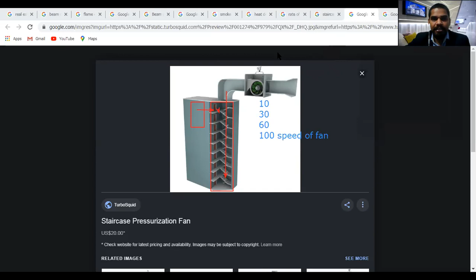For example, if only three floors are affected, it will run the fan at 10% speed. If 30% of the floors are affected, it will run at 30%. If 60% of the building is affected, it will run the fan at 60% speed. If 100% of the floors are affected, then it will use 100% fan speed, because the frequency of the opening of the doors also matters for the pressurization. So such preciseness we have to take care of while designing.